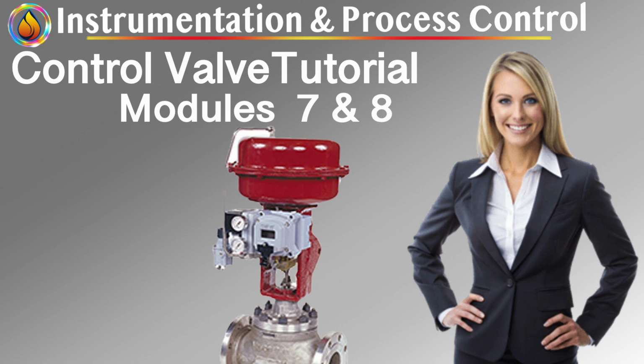Positioners and dynamic performance. Why positioners matter more than most engineers think. Positioners are often treated as optional accessories, added late, tuned casually, and blamed unfairly when loops misbehave. In reality, the positioner is the dynamic interpreter between the controller's intent and the valve's mechanical reality. If the actuator is the muscle, the positioner is the nervous system. Ignore it, and even a perfectly sized valve actuator pair becomes unpredictable.